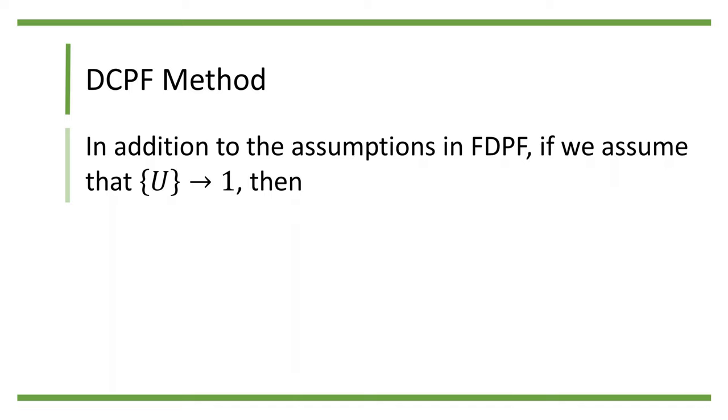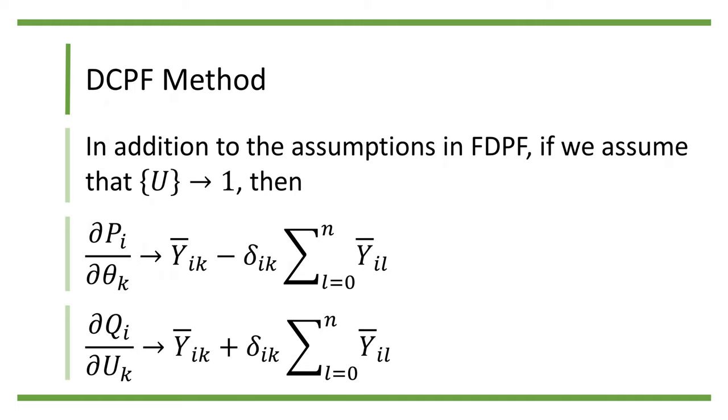For DCPF, we take a step further and assume that all the voltage magnitudes approach 1. Then, partial Pi over partial theta k approaches y bar ik minus delta ik summation l from 0 to n y bar il, while partial Q over partial uk approaches y bar ik plus delta ik summation l from 0 to n y bar il.